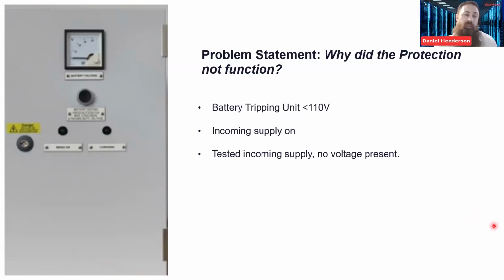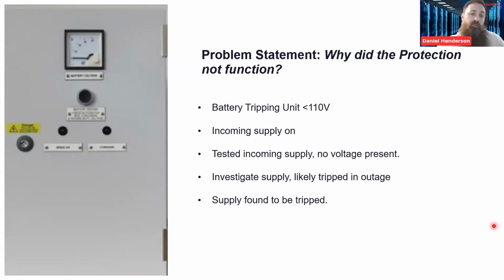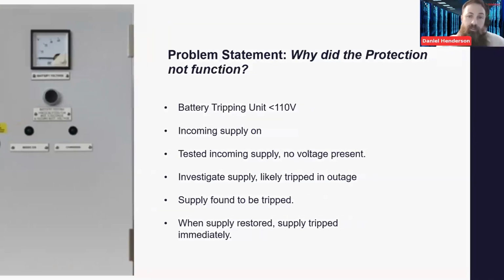A lot of the newer ones give you an indication on the front, and sometimes outputs as well to feed into your SCADA system or your BMS to say that there's no incoming charging voltage, but here there's no voltage present. So I presumed the breaker that feeds it had tripped when we had the outage. I investigated the supply and found that the MCB in the distribution board was tripped. I closed that on and the supply tripped immediately. So I've now got to investigate this further.